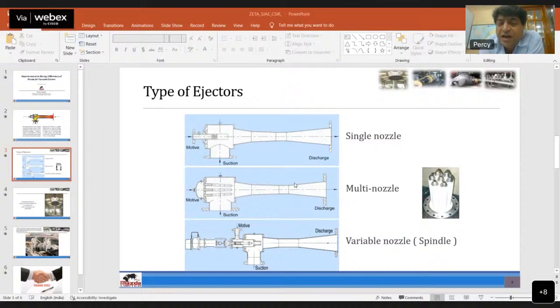The third ejector that we have developed is that a control valve is coupled with the steam ejector, and depending upon the turn down application, the spindle of the control valve moves in and out of the nozzle and reduces the cross section area of the nozzle and allows less or more amount of steam to pass through the ejector when operating at part load conditions.